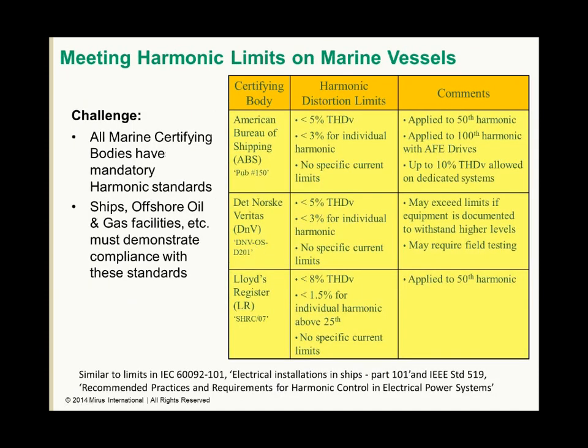The next case study I'd like to share with you is an application where a marine certifying body's harmonic limits needed to be met on a cable-laying vessel known as the Ocean Challenger. All marine certifying bodies have mandatory harmonic limits because of harmonic problems that are widespread on ships. This is because much of the load can be nonlinear and the power sources are relatively weak generator systems, leading to high levels of voltage distortion.